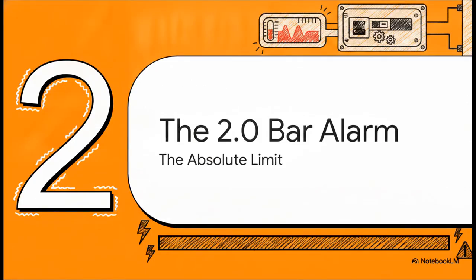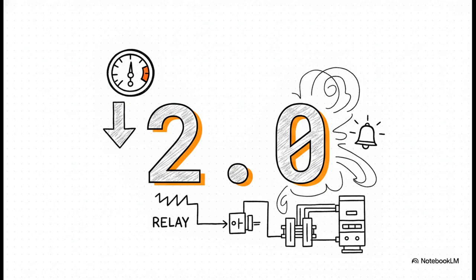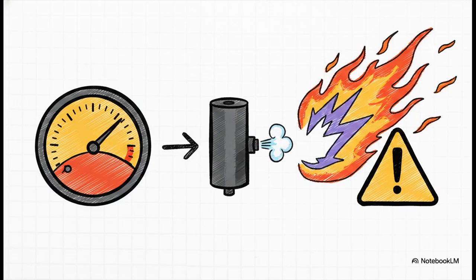Section 2. The 2.0 bar alarm, the absolute limit. Now, while temperatures and fill targets bounce around, the absolute safety limits of this breaker absolutely do not. There is a hard floor here, and that limit is 2.0 bar. If the pressure drops to this exact single number, a density relay immediately triggers a system-wide alarm. It's the absolute lowest safe operating pressure. Let me be super clear about this. That 2.0 bar threshold is not a mild suggestion. It's a hard, non-negotiable safety boundary. It is literally the line between function and failure.